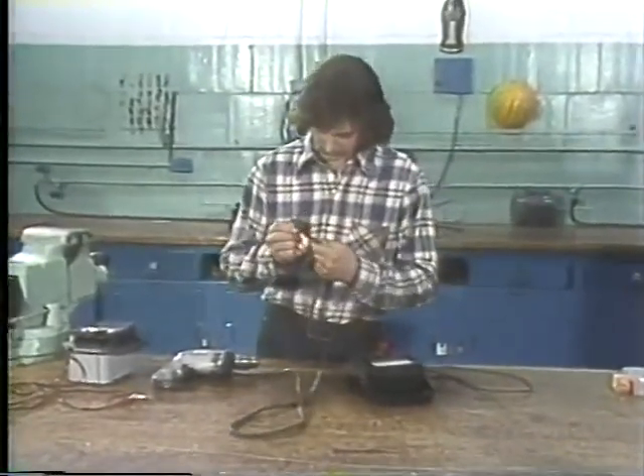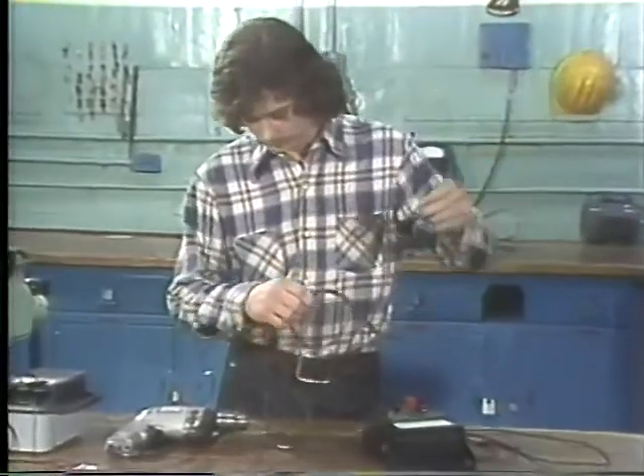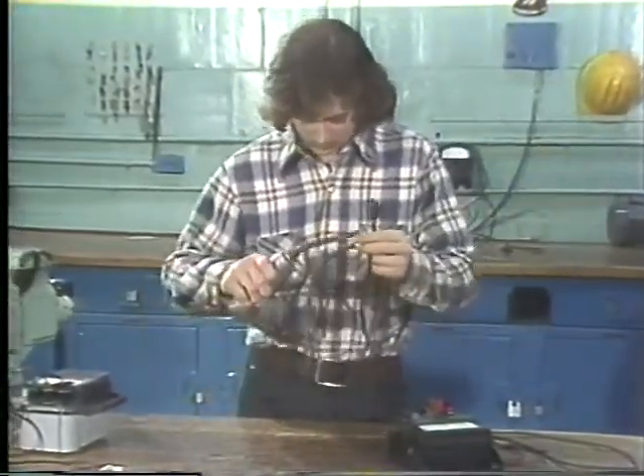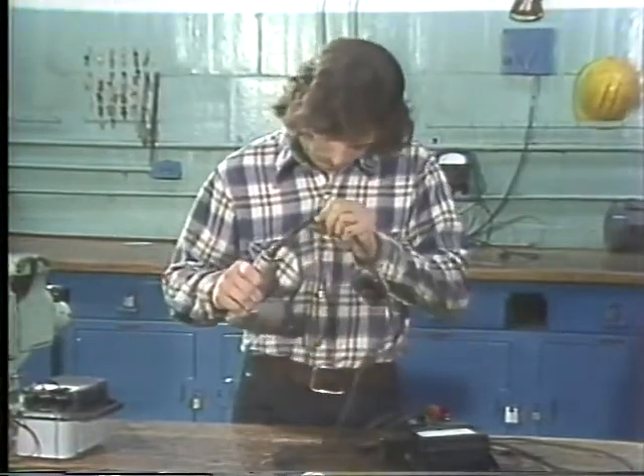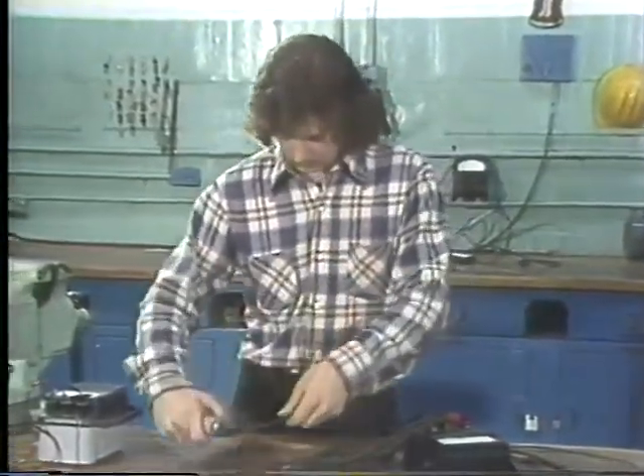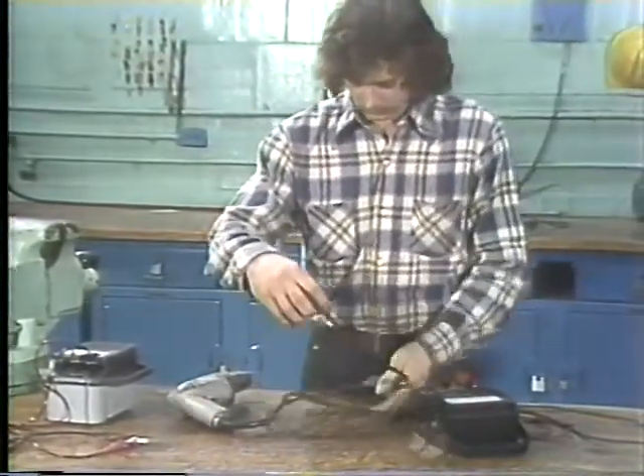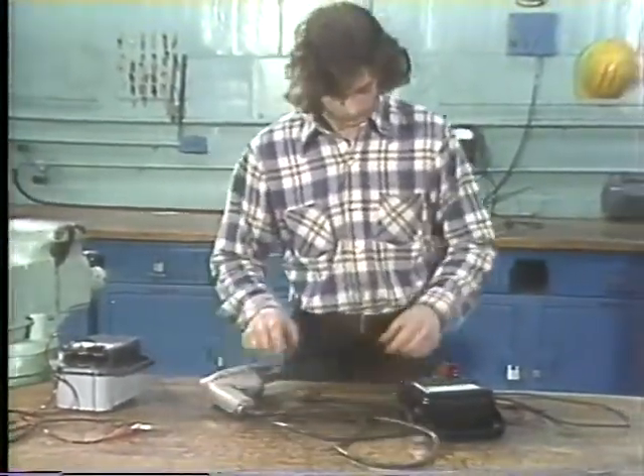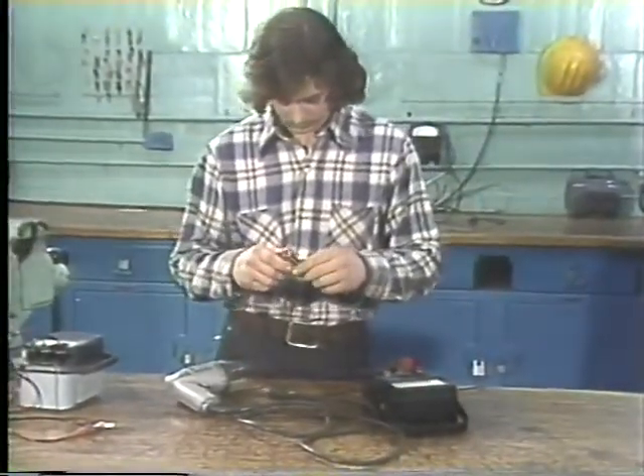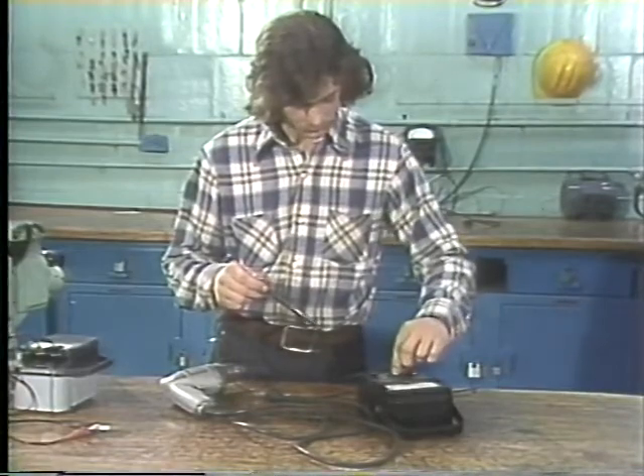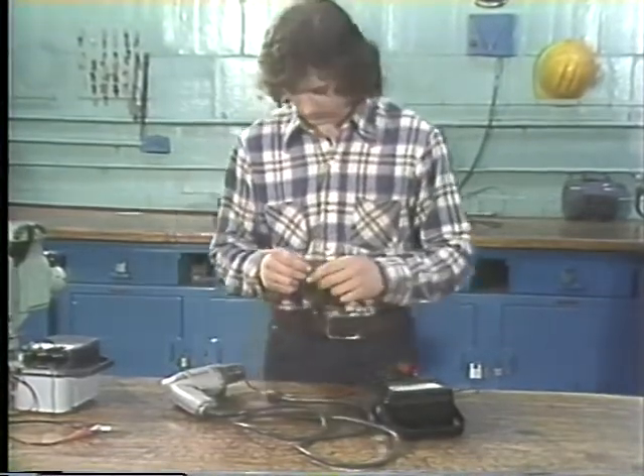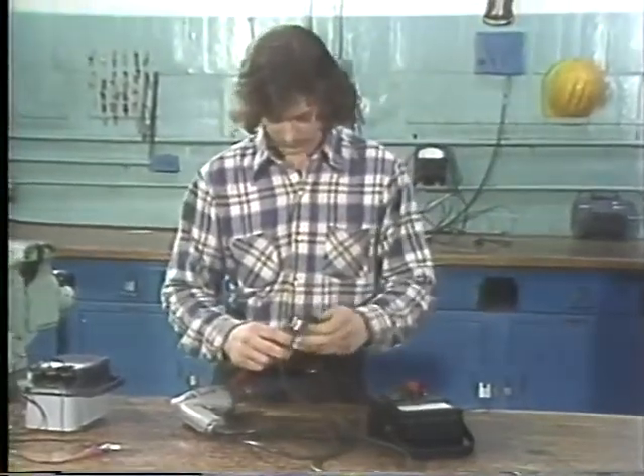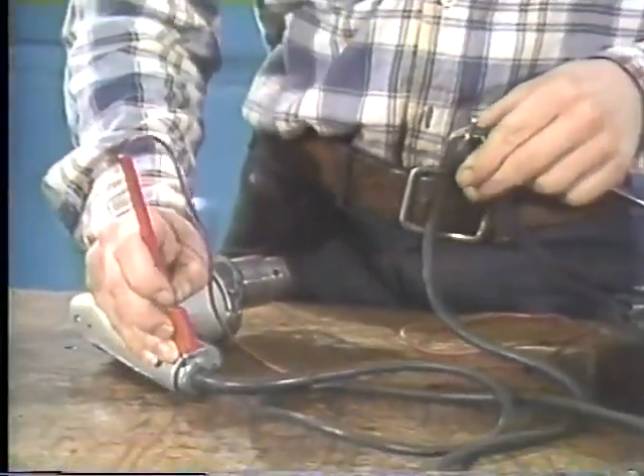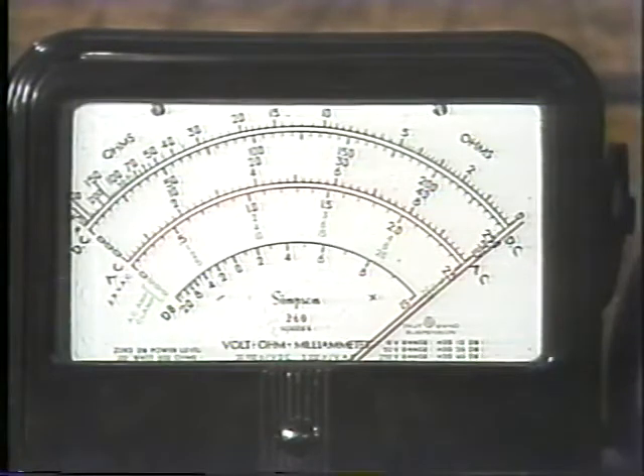The power cord is the place to start. Frayed or damaged cords are cause for many accidental shocks. If the cord looks okay visually, the next step is to check the drill electrically. This electrician's going to use a multimeter to check the continuity of the drill's ground conductor. He puts the selector switch on ohms and touches the probes together to zero the meter. Now he's ready to start the test. One probe goes on the plug's ground conductor and the other goes to the casing of the tool. The meter reads 0 ohms, so the tool's casing has a good conductor to ground.